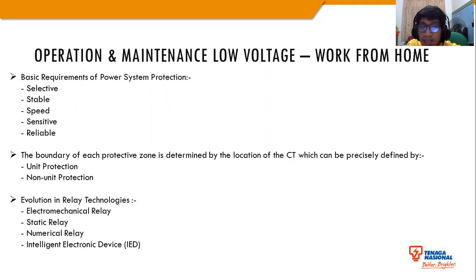electromechanical relay, static relay, numerical relay, and IED, intelligent electronic device. The latest one is IED. It's a second generation of microprocessor numerical based relay. It has versatile electrical protection, advanced local control intelligence, monitoring abilities, and the capability of extensive communication directly to a SCADA system.